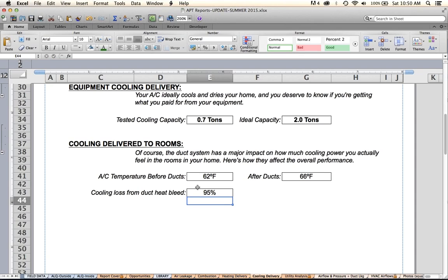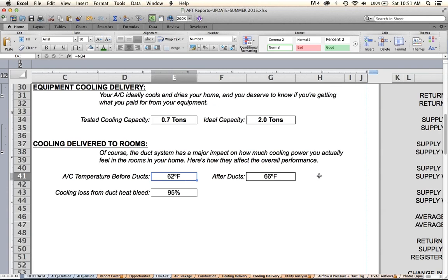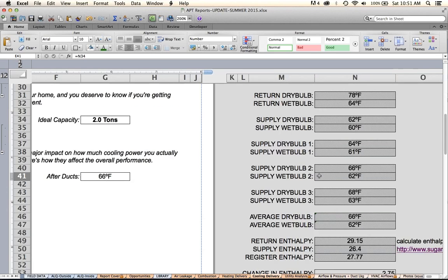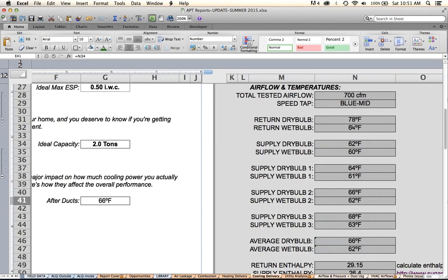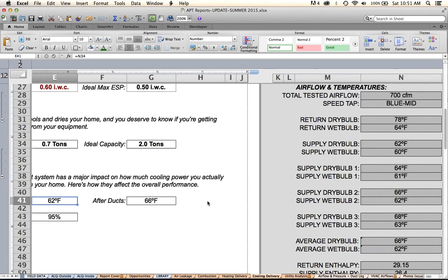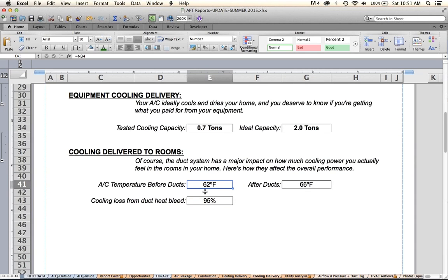Get rid of these here. I'm going to save. Well, anyway, you can see what we're going to be doing here. So I'm going to basically take this temperature loss that we got here, where it was down at 62, and then all of a sudden when it came out of the supply registers, it was all the way back up at 66, and the room temperature, the return temp, is 78. So that seems wrong. Anyway, we're going to build that in. 95 seems pretty high. I think that's wrong, so I need to check my math on that.